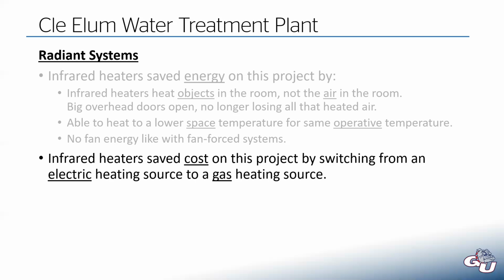The only downside to these infrared heaters is there really isn't an electric equivalent, at least not at this size or magnitude of heater. More and more, we're seeing owners say they don't want gas in their building and want to go to electric sources instead, and that's becoming more common. If that's the case, infrared heaters just won't work, so that's the only potential downside. But if you have a building with gas, or a customer okay with using gas, which most are, this is an awesome way to heat a big, large open space like this water treatment plant, or something like a warehouse or a shop.